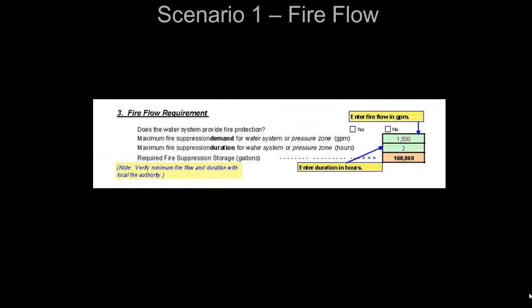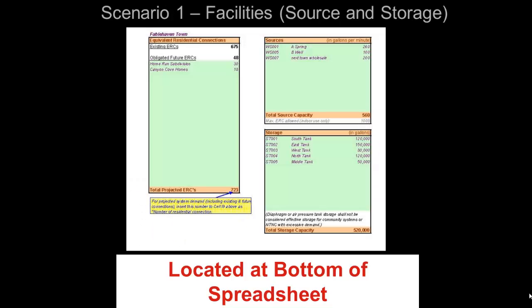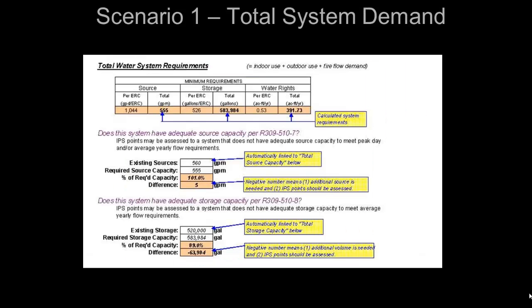Next, we'll input our fire flow demands. By entering 1,500 gallons per minute for 2 hours, the 180,000-gallon volume is automatically calculated. At the bottom of the spreadsheet, we enter the source and storage tank info and the associated flows and volumes — the totals are automatically calculated. For our scenario, this system has a total of 560 gallons per minute available from their sources and 520,000 gallons of total storage. Under the section for equivalent residential connections, you are able to input future obligated connections to verify that the system is able to handle anticipated growth. The total water system requirements are automatically calculated.